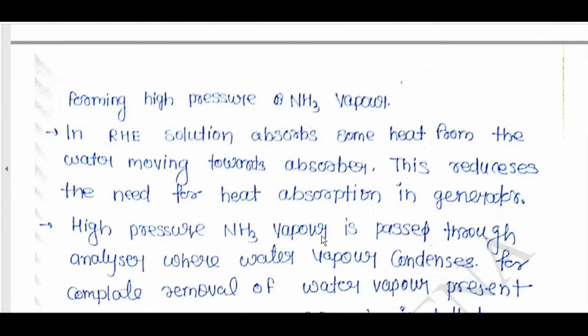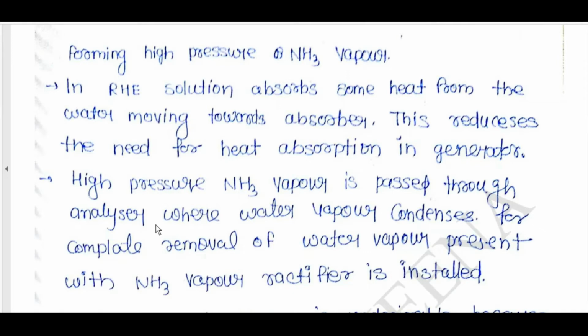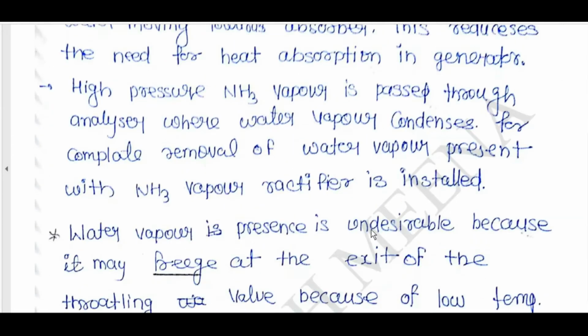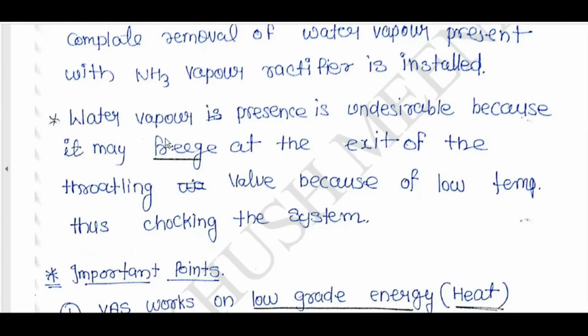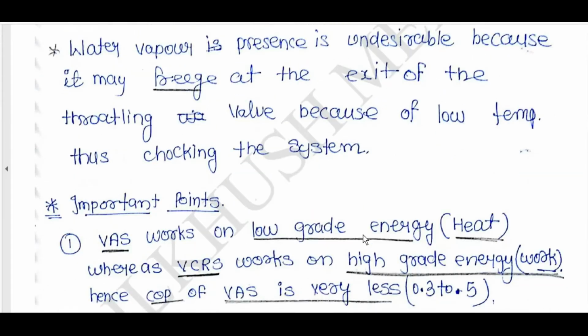High pressure NH3 vapor is passed through the analyzer where water vapor condenses. For complete removal of water vapor present with NH3 vapor, a rectifier is installed. Water vapor presence is undesirable because it may freeze at the exit of the throttling valve because of low temperature, thus choking of the system may occur.